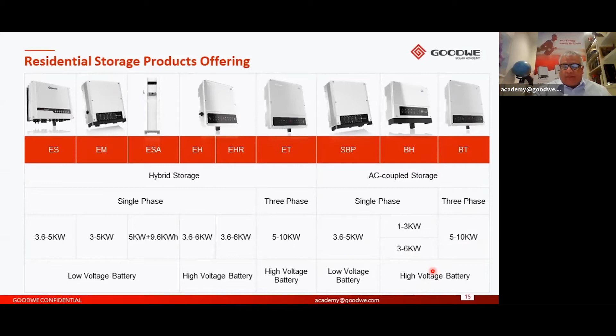Let's focus on the ES — the ES and EM are the ones we've been successfully selling in UK, Ireland and South Africa. Across the range, whether ES or EM, all the DC hybrids have an automatic switchover to backup: if the grid fails, within 10 milliseconds the hybrid switches to backup and you can run your load off the battery. You can also charge your battery from the grid in certain scenarios — not so much in the UK, but for instance in South Africa, if you have a bad PV day and know the grid will be turned off the next day in Johannesburg, you can charge your batteries from the grid so you have power for essential circuits when the grid fails the following day.